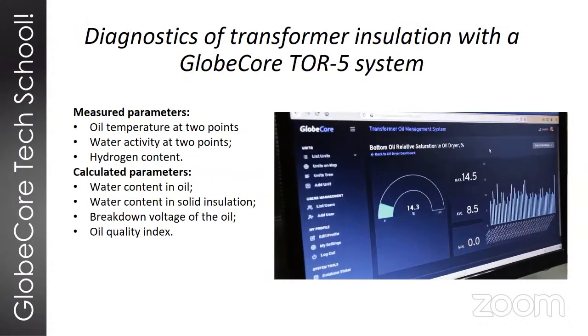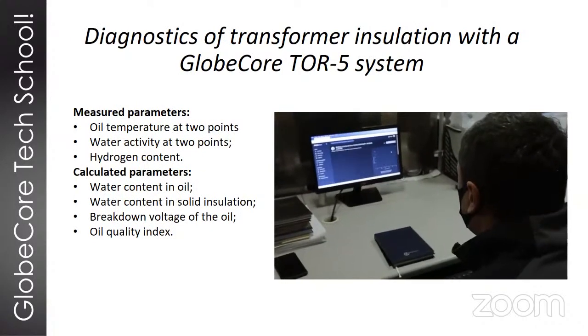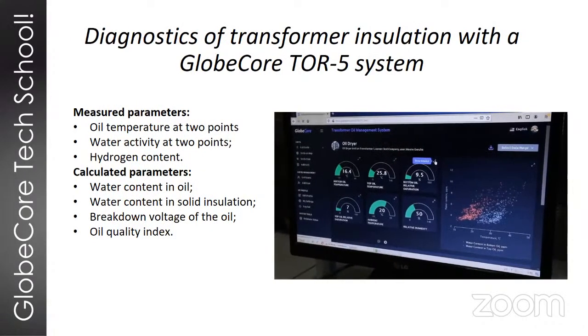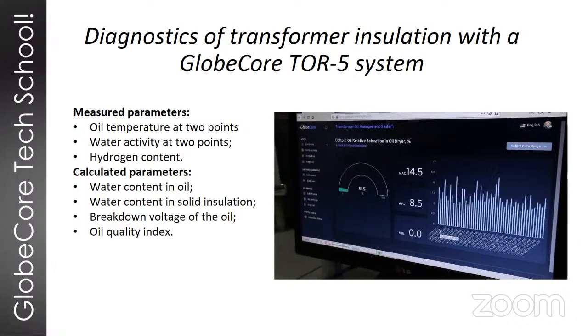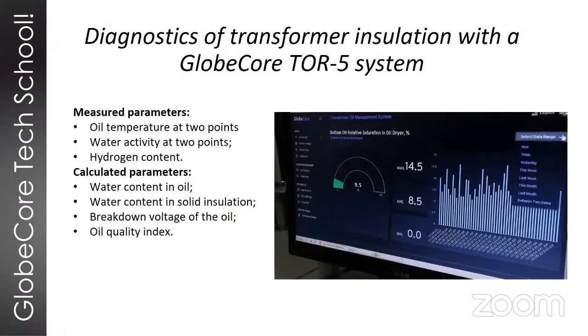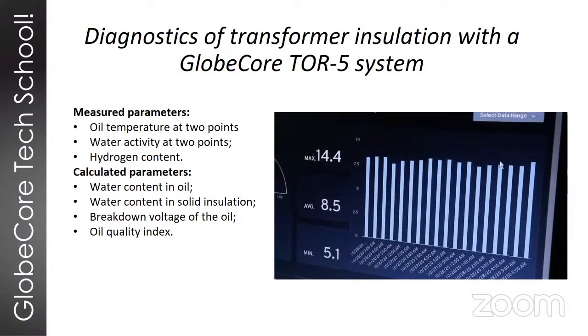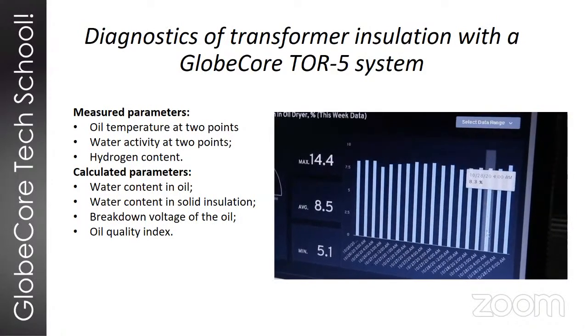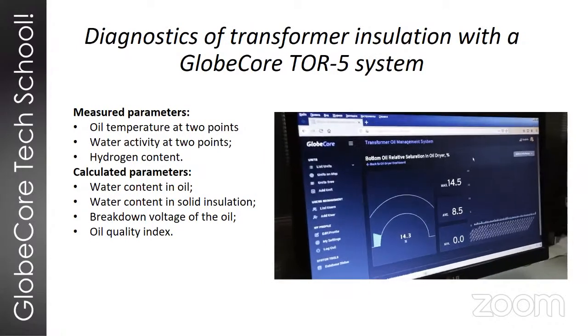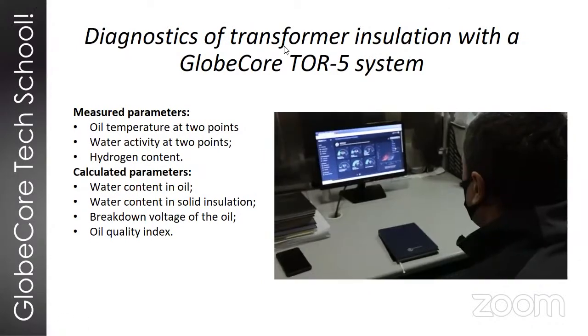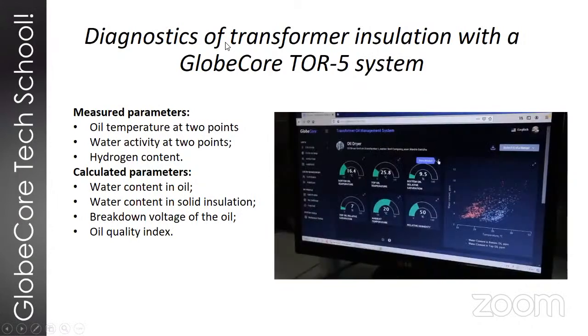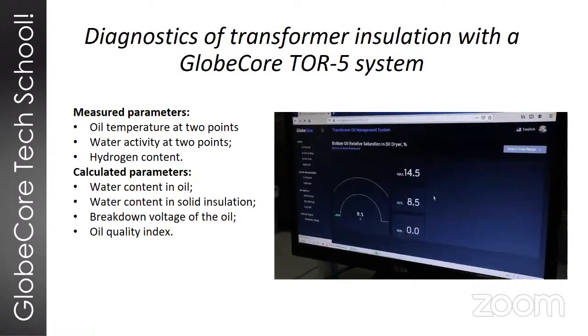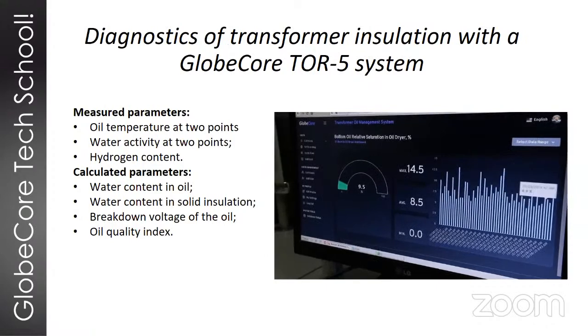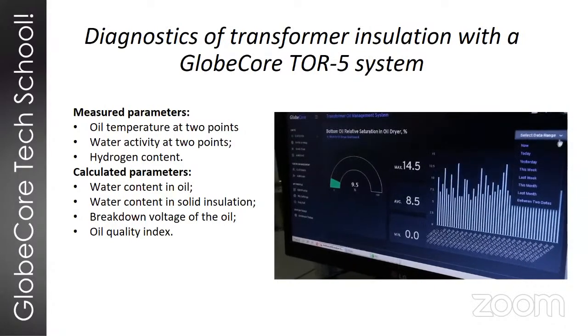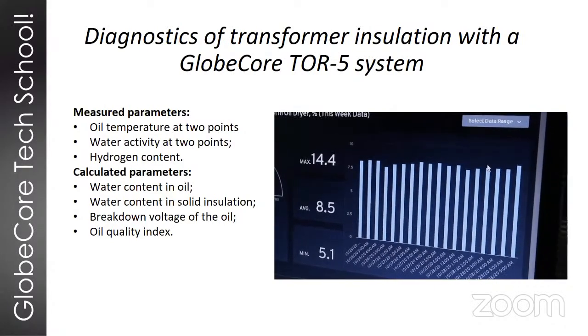All right, so the system has quite a few sensors. It has a router for connection and special software designed by GlobeCore. This system is installed directly on the transformer to be monitored, and it continuously collects data from those sensors. And using that data, the system calculates quality indices that allow us to see the actual quality of the oil and its moisture content. It can also give us an indication of the amount of water in the solid insulation.